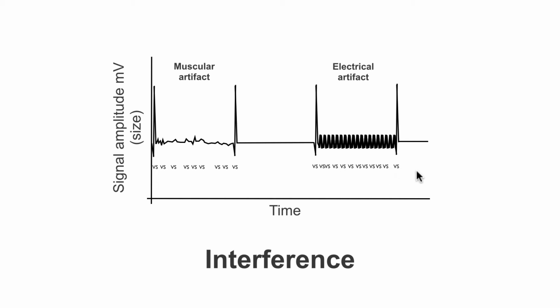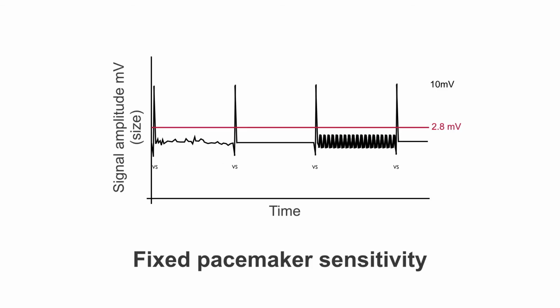So, we use a very simple tool to remove this artifact and this confusion from the pacemaker's decision-making process. We use something called fixed pacemaker sensitivity. Now, it's really quite simple. All we do is set a fence for the pacemaker, and we say you are to ignore all signals that are less than, for example, 2.8 millivolts in amplitude. You can see here that has meant that all this artifact is ignored, but all the genuine heartbeats, or the ventricular activity that is larger than 2.8 millivolts, is still being seen and still being registered by the pacemaker. And that is enough to ensure that the pacemaker sees things much clearer.